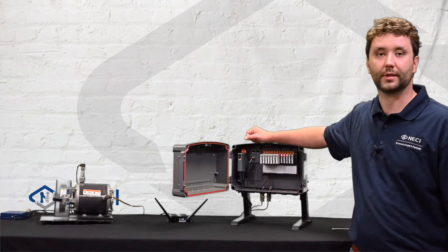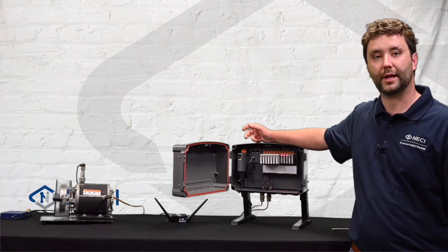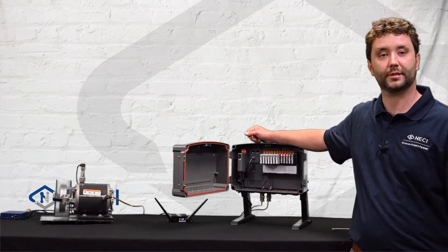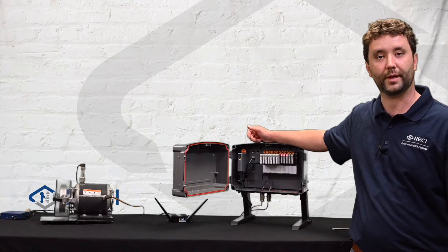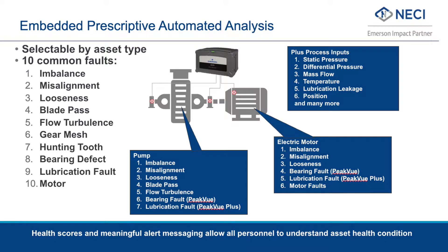The onboard processor provides built-in analytics to determine fault codes. This edge analytics device processes data and runs logic locally to make a determination of machine health. The onboard processor in AMS Asset Monitor can determine several common faults such as imbalance, misalignment, bearing defects, and other very specific machine conditions as shown on this slide. This is key functionality that is enabled by Emerson's long history of vibration analysis expertise.